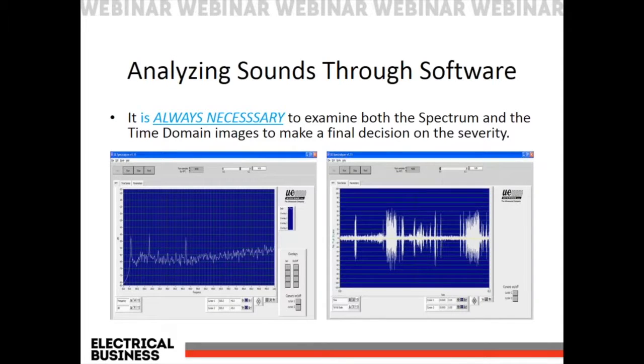Okay. So how does ultrasound work? How do we do this? Well, we're using this technology to look for a problem and hear a problem. When we hear something, we then take our technology and record the sounds to diagnose what we're hearing. If we don't do that, it becomes a little subjective. So we're listening to a panel and there's a sound in there. First of all, do we know it's electrical or mechanical? And secondly, if it is electrical, what is going on behind there? Can we open it up safely without testing the waters, as you'd say? So we go through analysis of the sounds through our software to understand what we're looking at here, and what we're seeing that these sounds make in the spectral analysis.